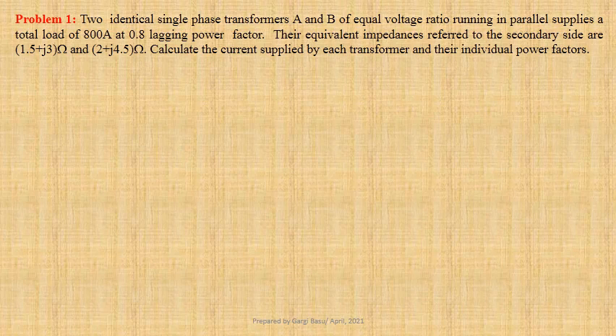Two identical single-phase transformers A and B of equal voltage ratio running in parallel supply a total load of 800 ampere at 0.8 lagging power factor. Their equivalent impedances referred to the secondary side are 1.5 plus J3 ohm and 2 plus J4.5 ohm. We have to determine the current supplied by each transformer and their individual power factors. Let us first write down the given data.